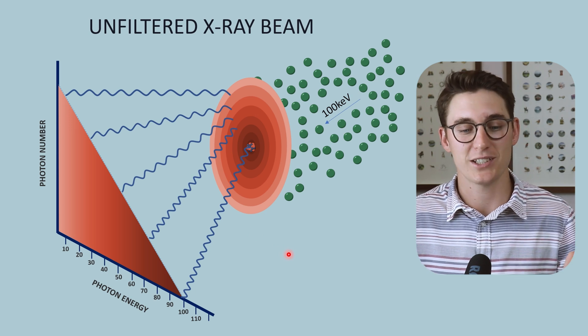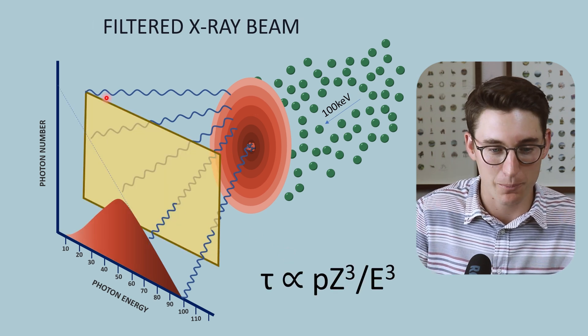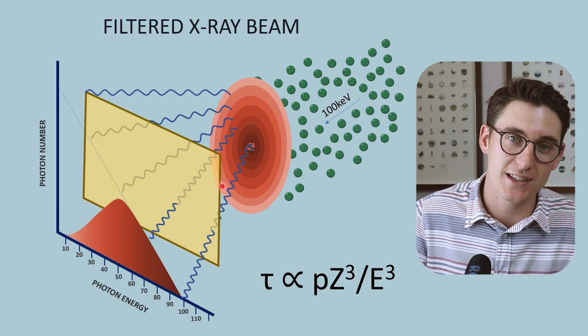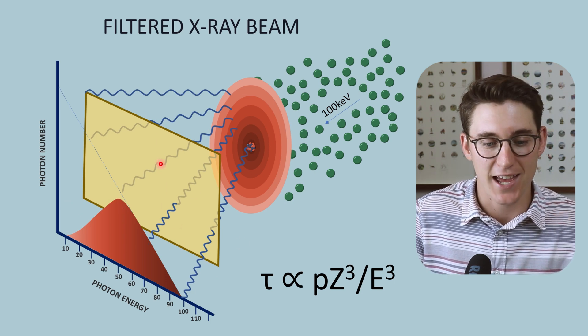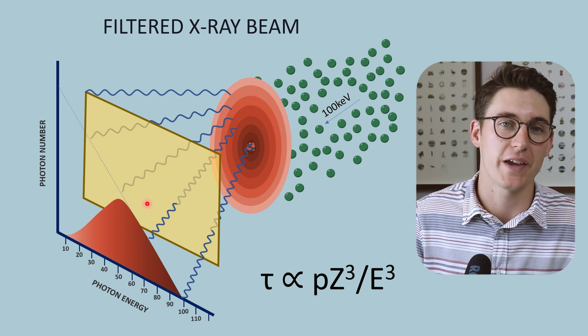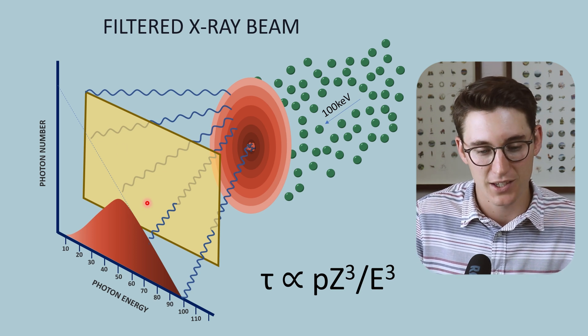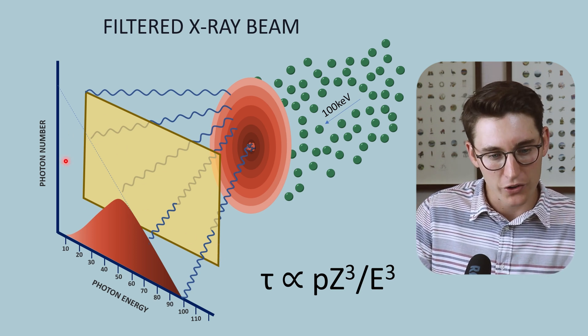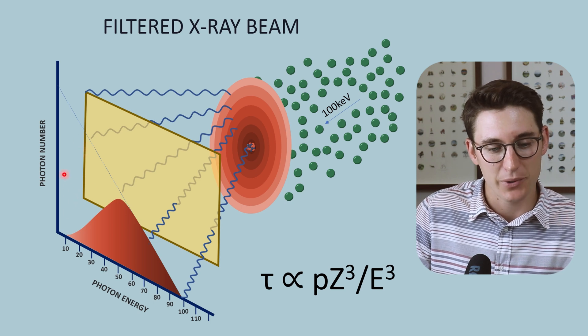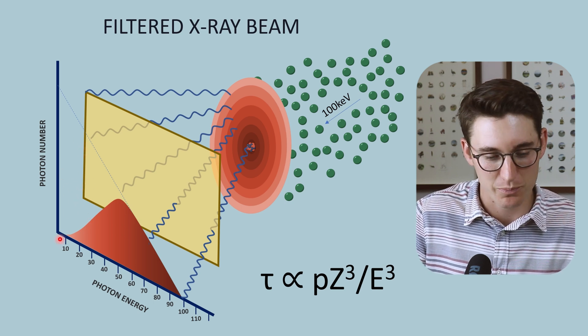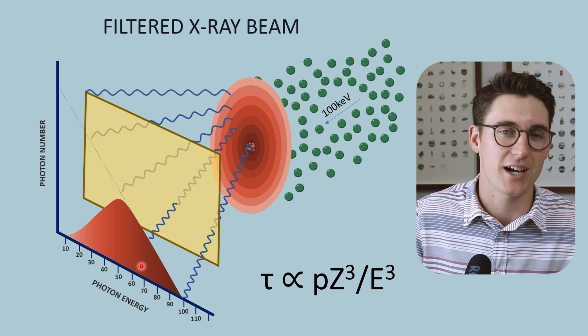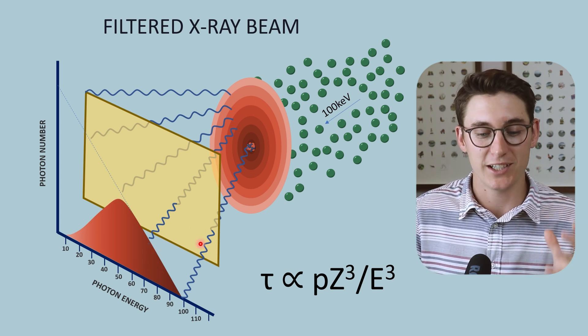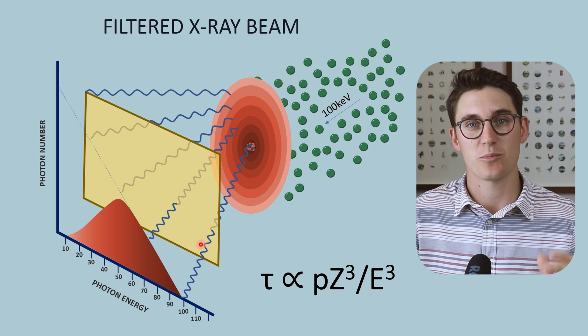What we can do is filter these x-rays. We can place a sheet of material between the anode and our patient to reduce the number of x-rays that reach our patient. The key question is why are the low energy x-rays being removed from the spectrum while the high energy x-rays are kept? This is the fundamental concept we need to understand when it comes to filtration.